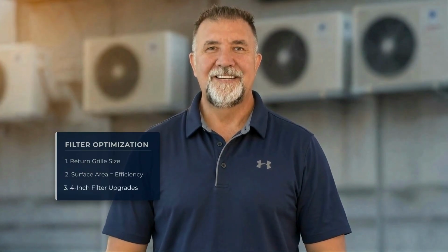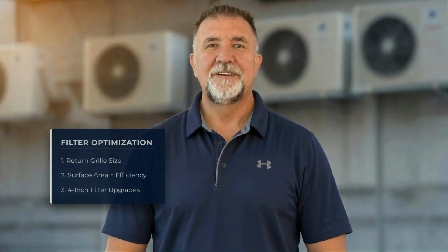Or let's say I have a 20 by 20 filter and I want a higher efficiency filter, but my system can't handle going to a MERV 13 in a single 1-inch filter. Well, I can have my HVAC company come out and put a 4-inch filter casing in, allowing me to go with a higher efficiency filter because, again, like we talked about, I have more surface area.